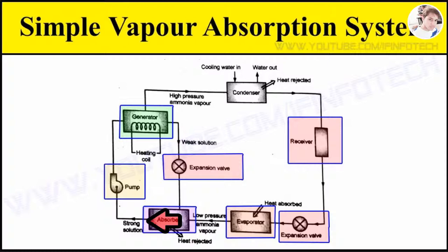In the absorber, the ammonia vapor is absorbed by the weak solution which contains less ammonia. Water has the ability to absorb very large quantities of ammonia vapor, and a strong aqua-ammonia solution is formed. Some form of cooling arrangement is provided, which is necessary in order to increase the absorption capacity of water, because at high temperatures water absorbs less ammonia vapor.